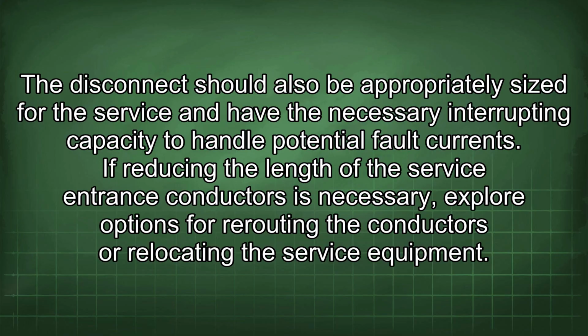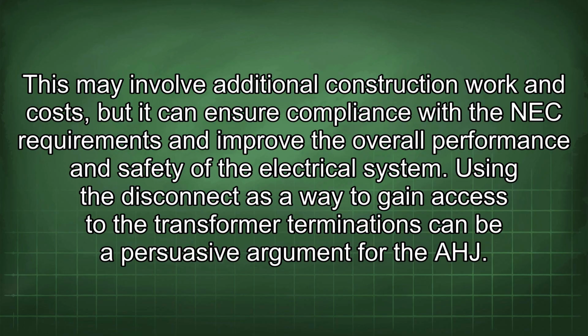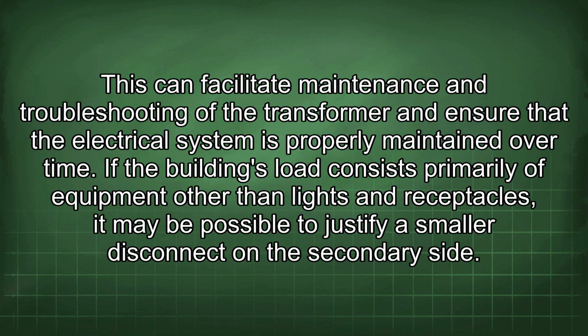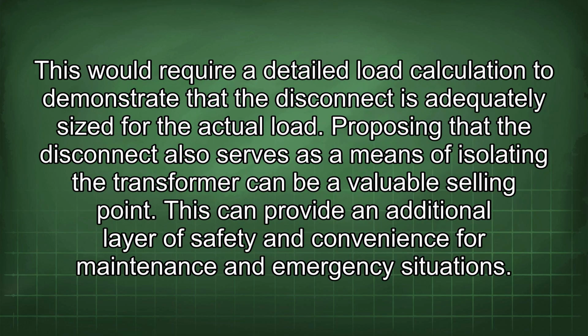If reducing the length of the service entrance conductors is necessary, explore options for rerouting the conductors or relocating the service equipment. This may involve additional construction work and costs, but it can ensure compliance with the NEC requirements and improve the overall performance and safety of the electrical system. Using the disconnect as a way to gain access to the transformer terminations can be a persuasive argument for the AHJ. This can facilitate maintenance and troubleshooting of the transformer and ensure that the electrical system is properly maintained over time. If the building's load consists primarily of equipment other than lights and receptacles, it may be possible to justify a smaller disconnect on the secondary side. This would require a detailed load calculation to demonstrate that the disconnect is adequately sized for the actual load.